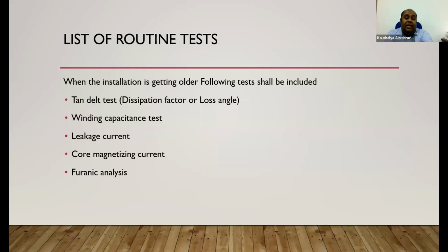If the system is getting older and older, you may have to do some other tests to check your insulation level, like tan delta and winding capacitance test and the leakage current test. If you are doing the tan delta test, you will get those two also during the test. Core magnetizing current for your transformers, and furanic analysis, especially for your oil immersed transformers. If you are exceeding maybe a lifespan of 15 years, it is recommended and shall be checked.